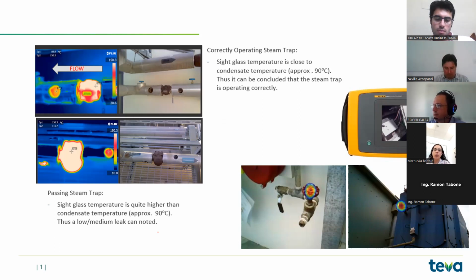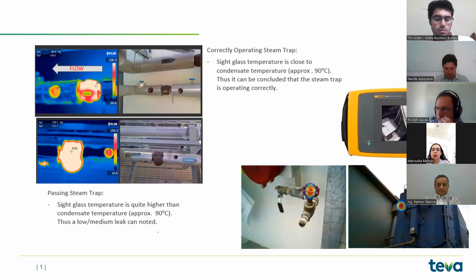And two projects that we are working on are how to make the systems more efficient through maintenance testing. So we have steam trap testing that was previously done using ultrasonic detection. However, ultrasonic has some disadvantages. One is that you need to go close to the steam trap. I have to use a ladder, so it's not that safe. So we changed to thermal imaging testing. It's easier for interpretation, the room for interpretation is less, so it is less prone to mistakes. And we get the same results.